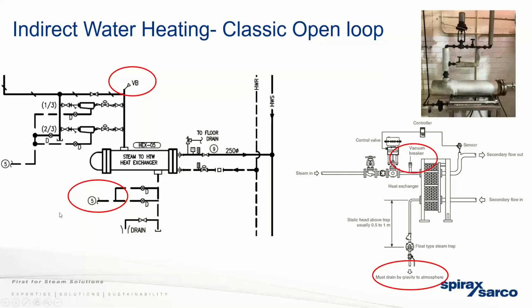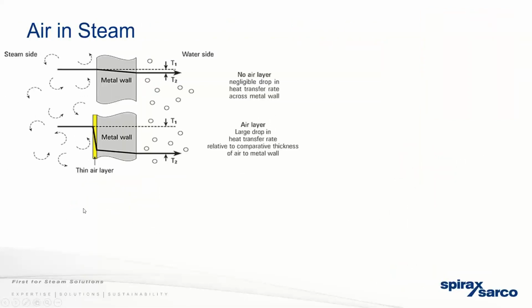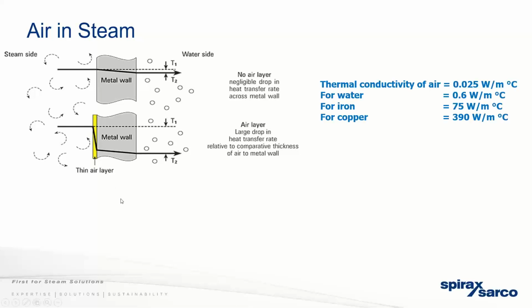So some negative things in this is that air in steam is an insulator. Air in general is an insulator. So you can see in this chart, if it was just the metal plate on the heat exchanger, you would have a slight loss in temperature across the plate. But if you have a film of air inside the steam side here, there's going to be a higher temperature drop. So the result is less heat available to heat your process.